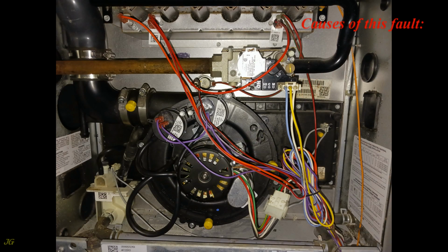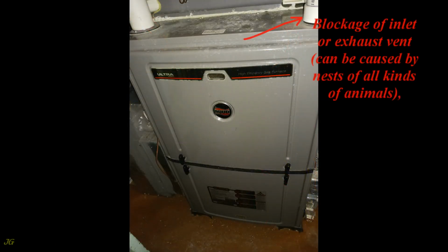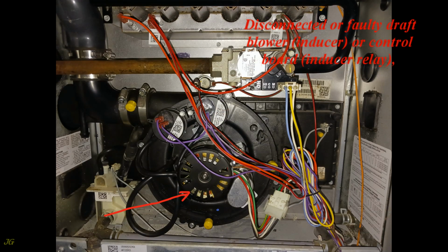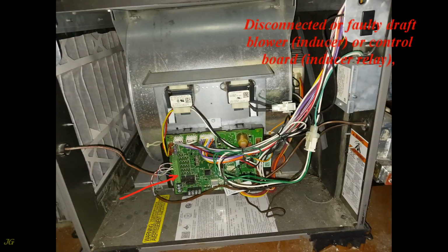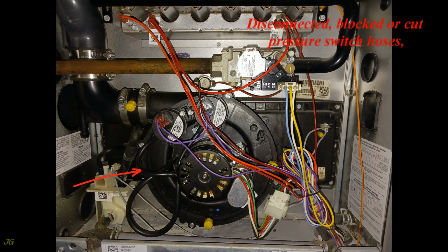Causes of this fault. Blockage of inlet or exhaust vent can be caused by nests of all kinds of animals. Disconnected or faulty draft blower, inducer, or control board, inducer relay. Disconnected, blocked or cut pressure switch hoses. Loose wiring. And most likely a non-working low pressure switch.